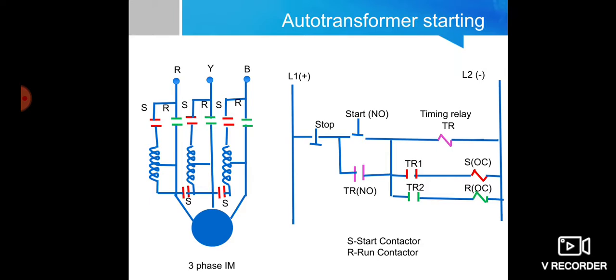So let us see how it operates. Obviously, starting with the start push button, you need to press the start push button because it is normally open. Unless and until you press it, it won't get closed. So let us push the start button. Now we have pushed the start button, because of which the timing relay coil should get energized. Now this TR will get energized, because of which all the contacts related to TR will get closed.